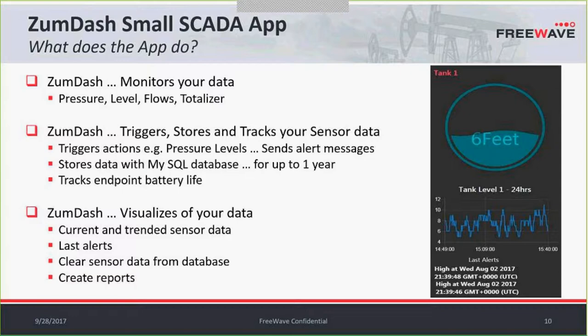With this functionality, you can install the app on a ZumLink or on the cloud and then transmit the data either directly from the ZumLink or from the cloud. ZumLink monitors analog, digital, or HART data interfaces through Modbus. It tracks your data and triggers alarms — for example, if you have a tank level that's high, turn off the pump — and you can command directly from the app. It stores data, and you can also send alarms to cell phones by text message, by email, or even post it on your Twitter account with Node-RED.